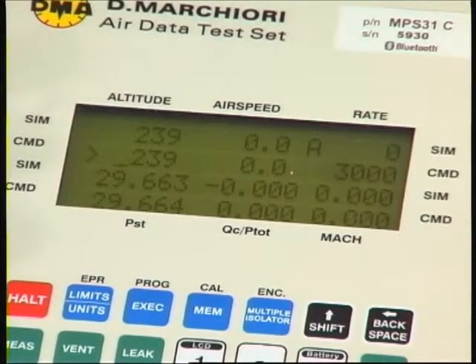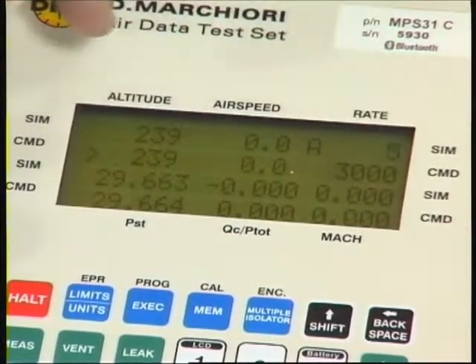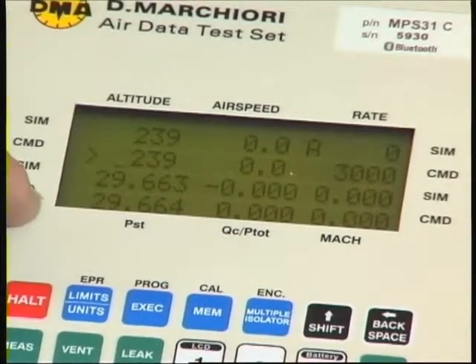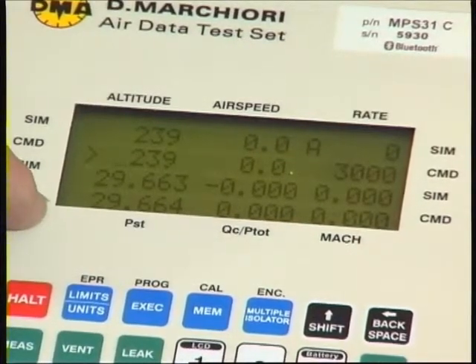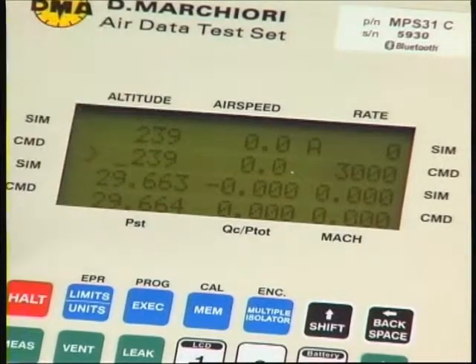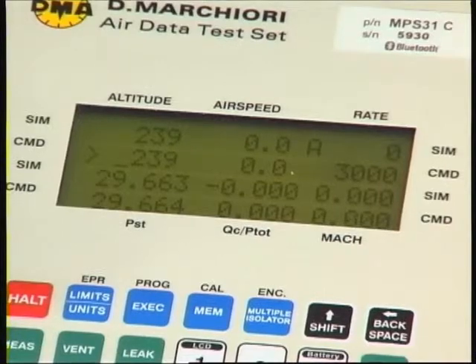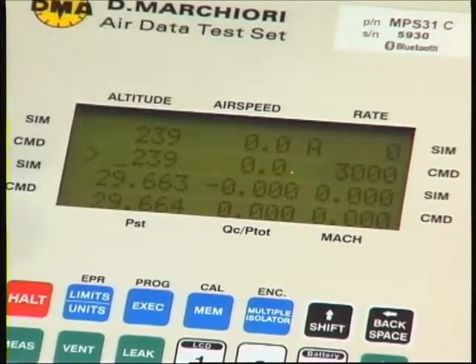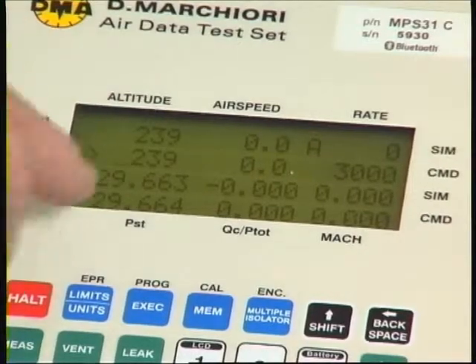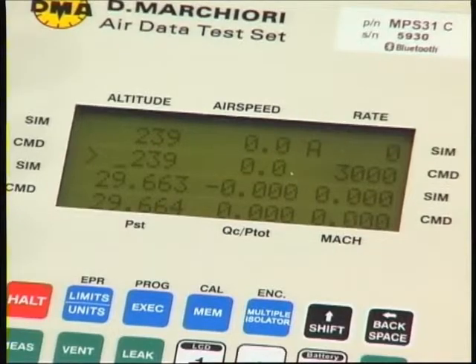The final two lines — simulated and command — are precisely the same situation as the first two but now they are in pressure units instead of aeronautical engineering units. We have the same values displayed in inches of mercury, which is the default on this instrument, although we have many alternatives which we will show you soon. So here we have the fact that apparently 239 feet altitude is equivalent to 29.663 inches of mercury.